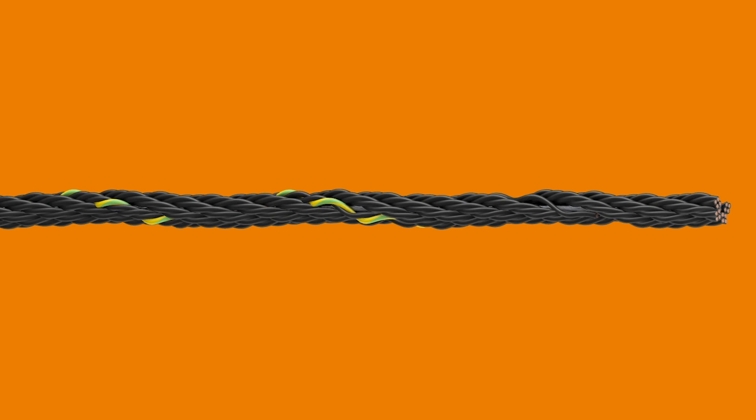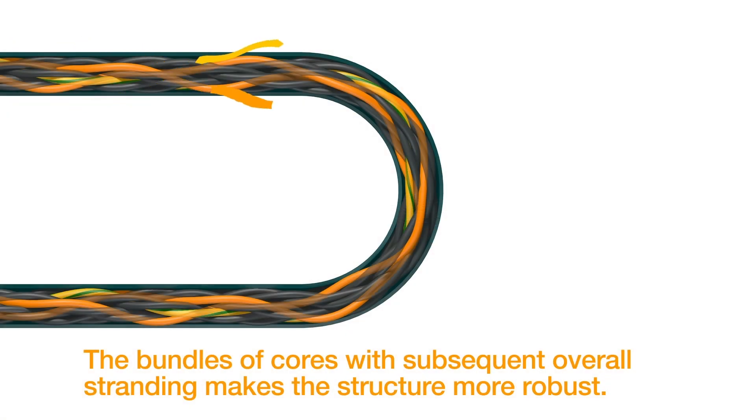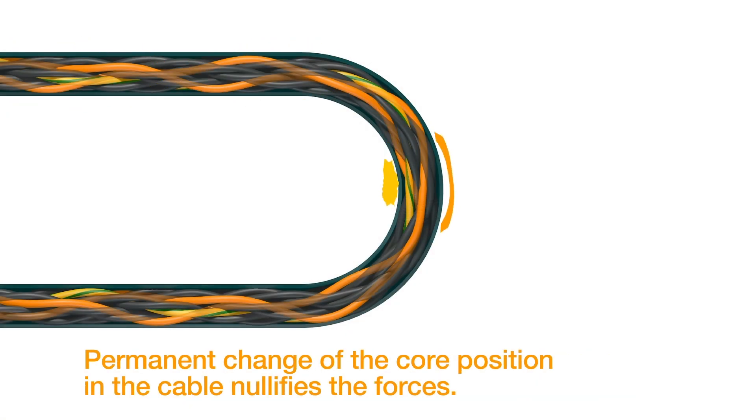That being said, all of igus' chainflex cables are engineered for continuous flexing environments. We do this by incorporating a center strain relieving element into the cable. The center strain relieving element takes the compression and tension off the conductors in continuous flexing environments, thus preventing corkscrew, as the conductors aren't being pushed to move anywhere they shouldn't be.